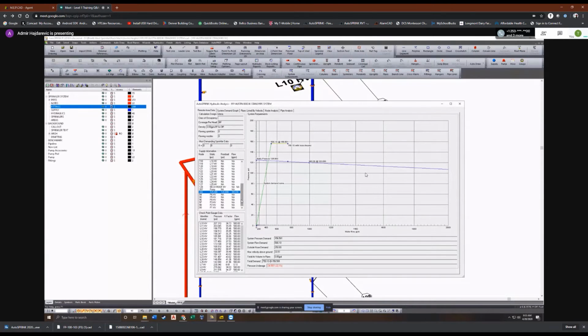Okay, so something else, just FYI, we are including an outside hose demand, and I don't know that that's necessarily appropriate for a standpipe calculation. So we might want to consider getting rid of that 250 outside hose. But the pressure underage is telling us that we have 34.5 psi less available than what we need. We need 34.5 more psi to get to the roof, to satisfy the demand of this system based on the minimum pressure and flow rates that we've established at the hose connections.